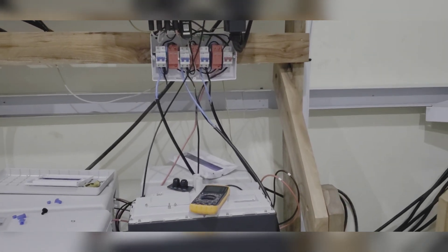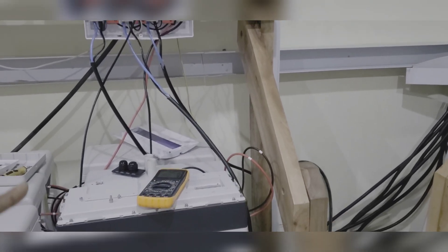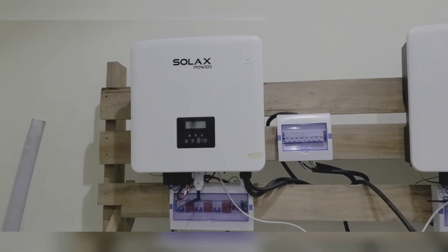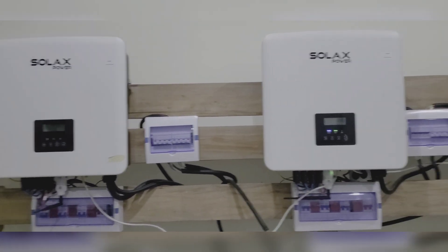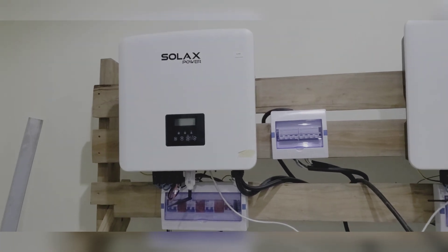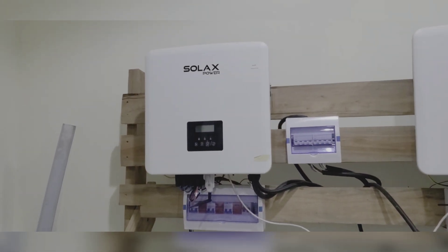This inverter — as you can see, all the cables are exposed because we are still trying to resolve the balancing issue. This inverter is having a communication issue. SolaX is going to take it back to the factory in China and send us a replacement. They're going to do a post-mortem, take it apart and find out why there's a communication issue. When we plug it in, we can set it as master and we have an issue, but we can set it as slave and all the other slaves work fine except this one. That's why it's being sent to China and they'll send us a replacement.